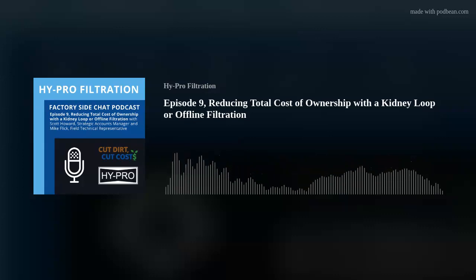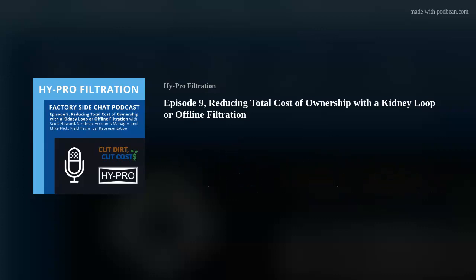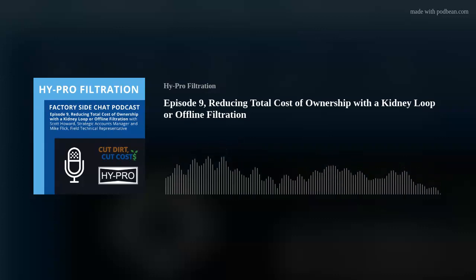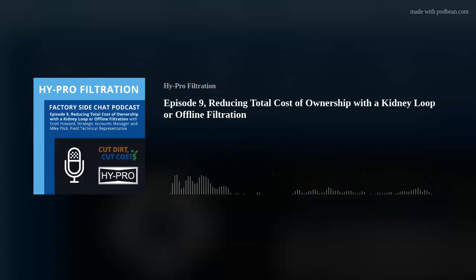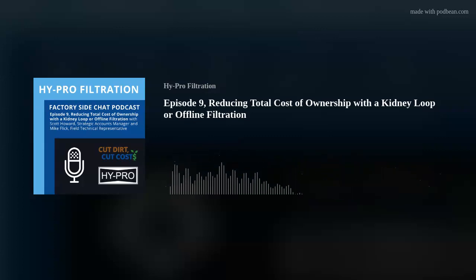Once we have that information, 9 times out of 10, the OEM or the original manufacturer probably either undersized or may have not put the adequate filtration in place for the machinery that they built. So when we look at that, I always like to make my recommendation on a fact base. So if we have unclean oil, I like to recommend a kidney loop.